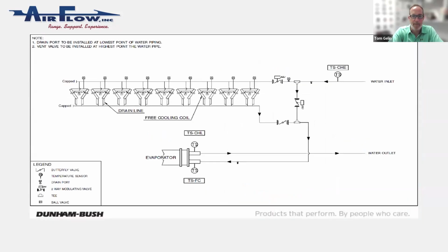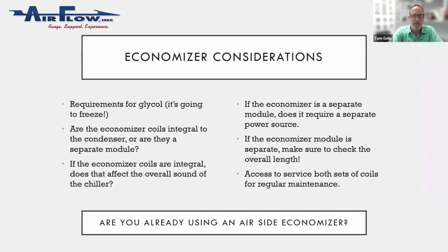this is just kind of that bypass piping that goes around. So some considerations: number one, unless you're completely shutting down your air-cooled chiller and draining it, you're going to have glycol. And how much glycol is sort of a function of if you're using free cooling or if it's just freeze protection. And then that next point, are the economizer coils integral to the condenser, or are they a separate module? So some air-cooled chillers will have a water coil and a refrigerant coil in series, and then the fan on top. So if you specify free cooling, you may actually get a separate section that's bolted on. And you may have a free cooling section and then a condenser section. So it's important to pay attention to that.